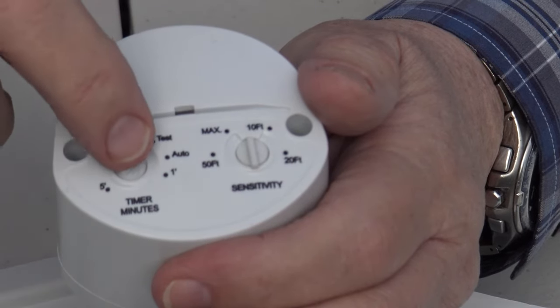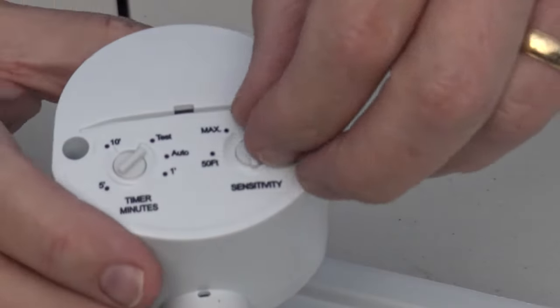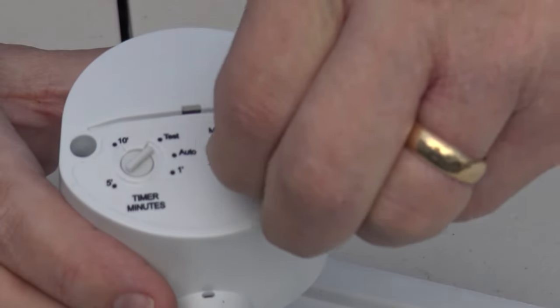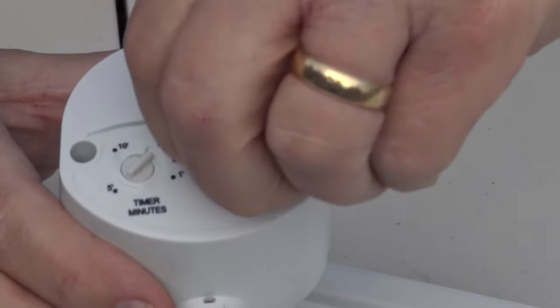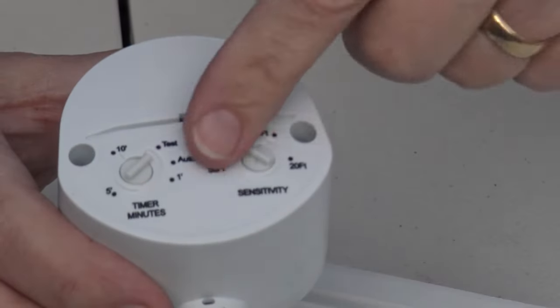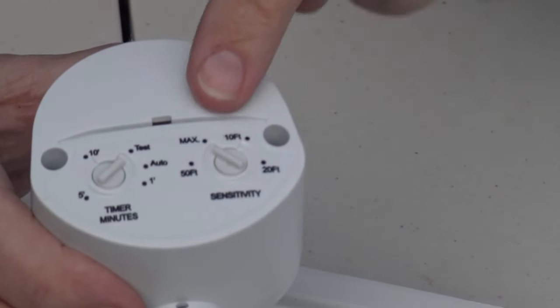When you walk side to side, you can then adjust your sensitivity here, where if you want it at 20 feet, or you want it at 30 feet, here's 50. The max on our particular unit for a 180 device is 70 feet.